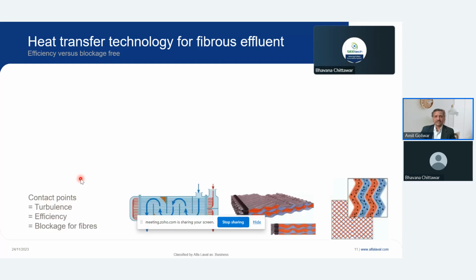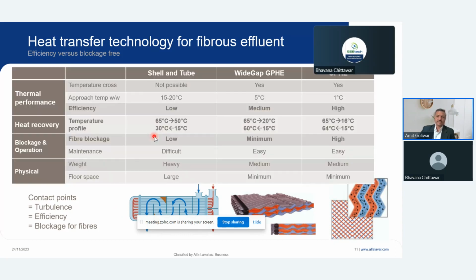If it is contaminated fluid, it is very difficult to use any heat exchanger. So typically, if you look at heat exchangers, you have a very efficient heat exchanger, which is a plate heat exchanger, and a heat exchanger where you can use fibrous or a slurry kind of liquid, which is a shell and tube. But then there are advantages and disadvantages of both. If you look at the advantages of shell and tube, the fibrous liquid can go, and if you look at the disadvantages of PHE, there the choking chances are high. However, there are some disadvantages of shell and tube, which I will cover in the next slide.